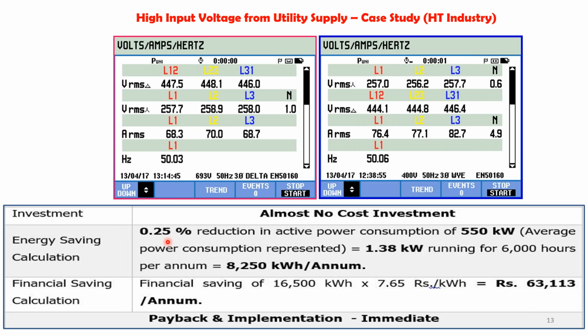That will give a small saving of 0.25%. As we know, V1 by V2 will be equal to P1 by P2. So as per this formula, if you slightly vary your voltage to the specified voltage, a minimum of 0.25% saving of your total consumption, where 550 kilowatt is the maximum power consumed by the industry. So the saving is going to be 1.3 kilowatt for 0.25%, and if the entire industry runs for 6,000 hours in a year, then the overall power saving for the entire year is going to be around 8,000 kilowatt hour. And the rate per kilowatt hour for the industry is around 7 rupees 65 paise. Even the amount is very small, even the unit saving is very small, but in terms of financial saving it is going to be around 63,000 rupees. So maintaining the proper voltage will help conserve energy, and it will also be more beneficial for the equipment.